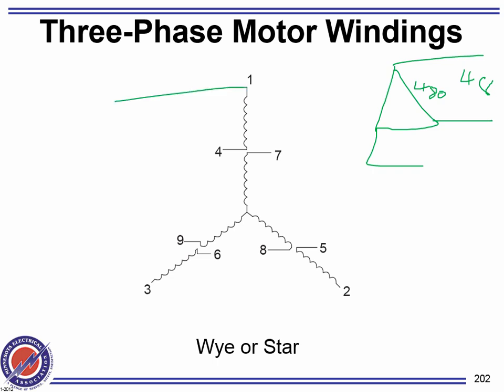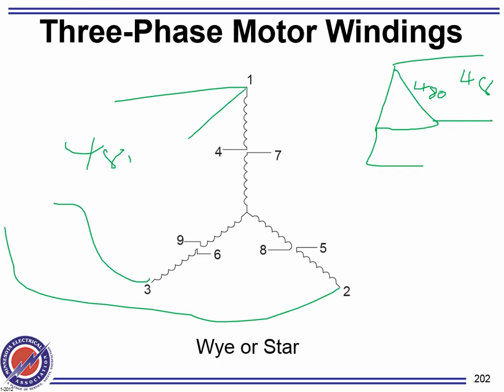Now, what happens if you put the 480 voltage here? What's the voltage across the coil? 277. That's almost half of that. So which one do you think is going to have more starting torque? The delta motor. They have more starting torque because they have more voltage across the coil, because that's what matters. By the way, if you want more torque, delta motors will get you more torque. Or one solution.